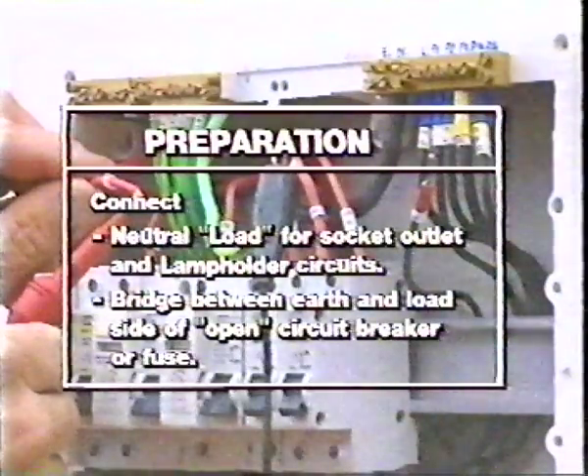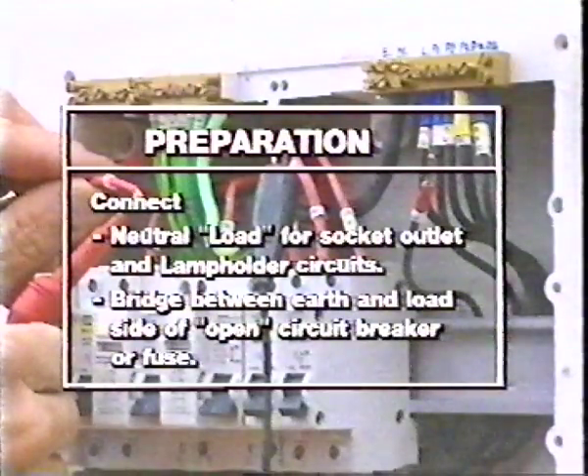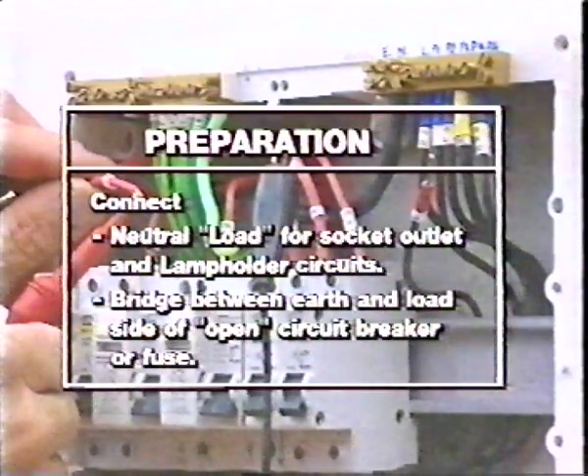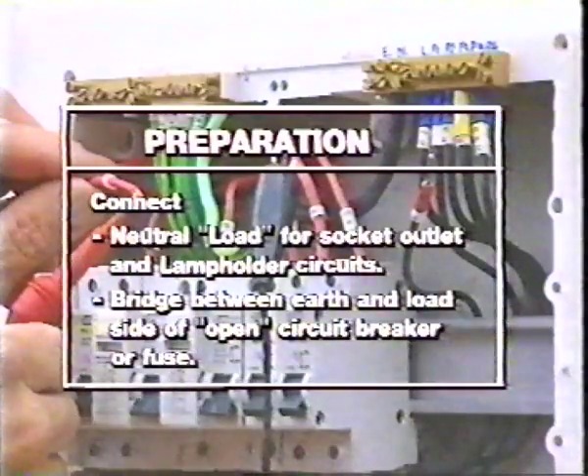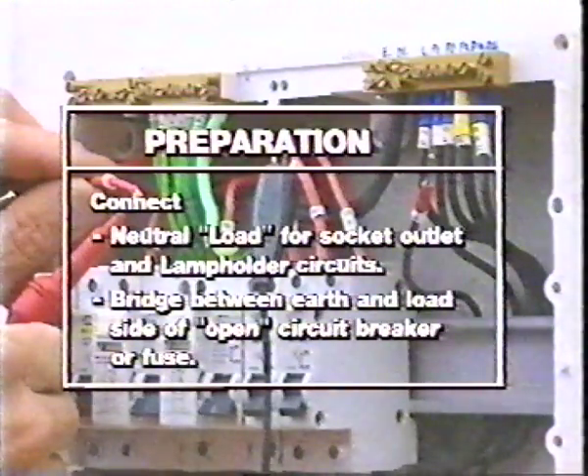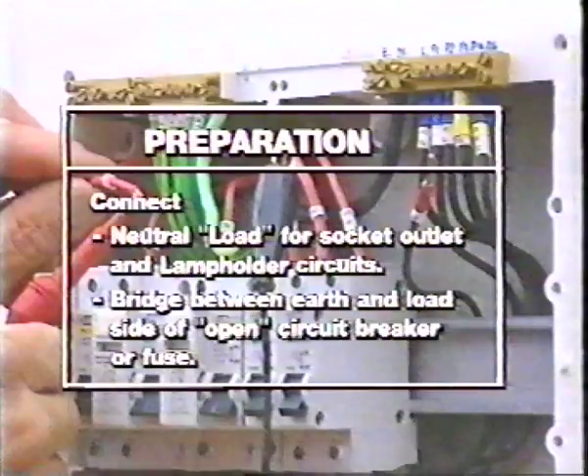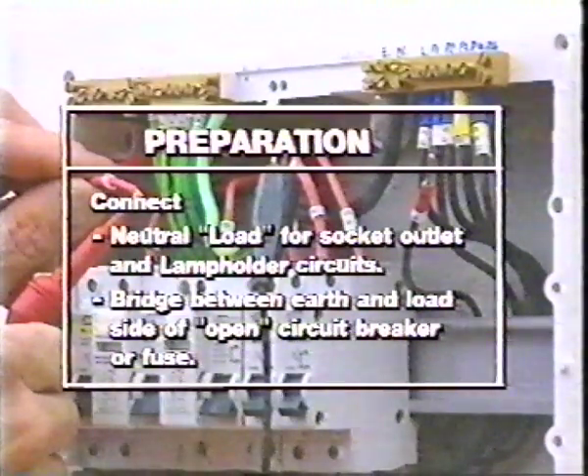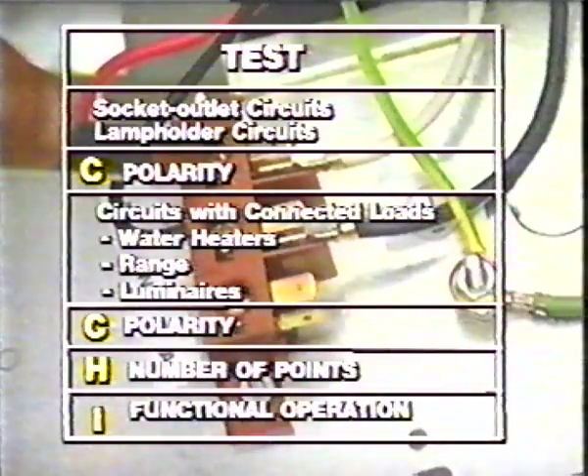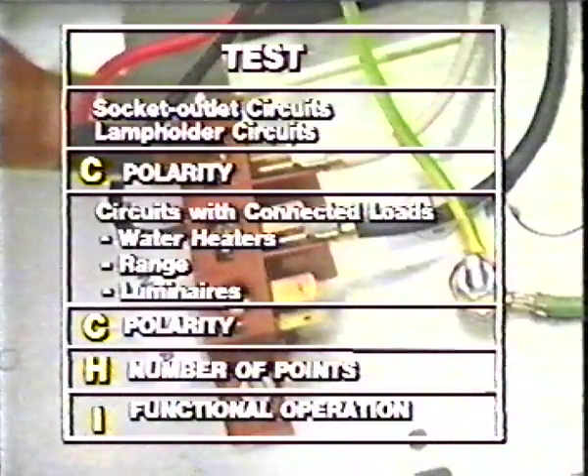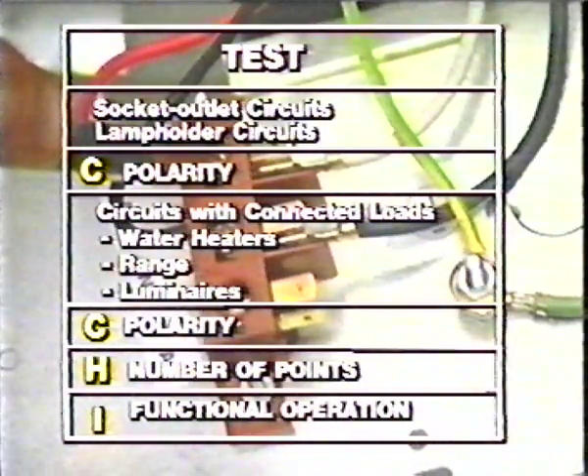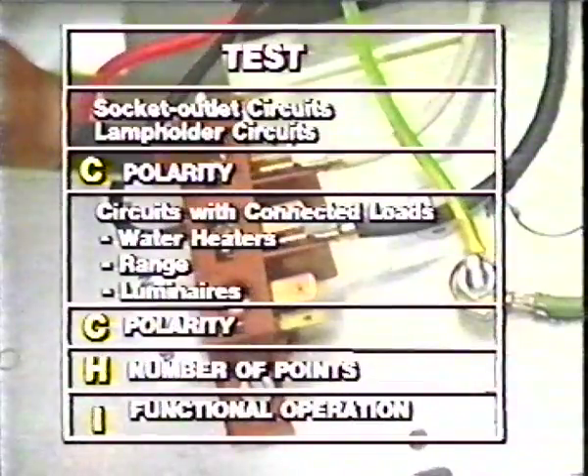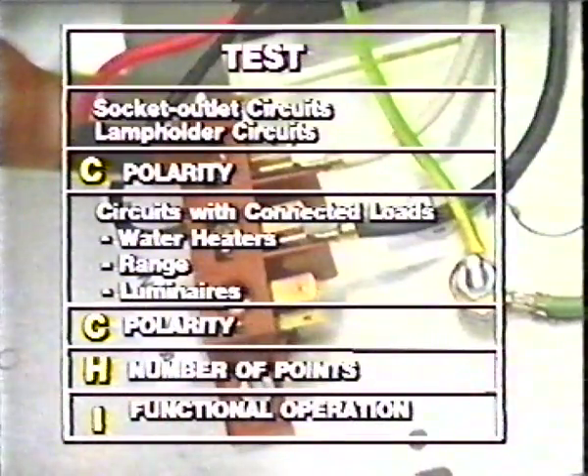To test for polarity in socket outlet and lighting circuits, the neutral load is connected as in test D, and a temporary connection made between earth and the load side of the final sub-circuit's open fuse or circuit breaker. Correct polarity will be proved when, with the switch on, active to earth indicates a short circuit and neutral to earth indicates load resistance. And with the switch off, active to earth indicates an open circuit and neutral to earth indicates load resistance.